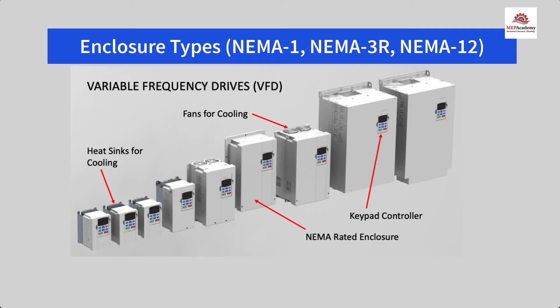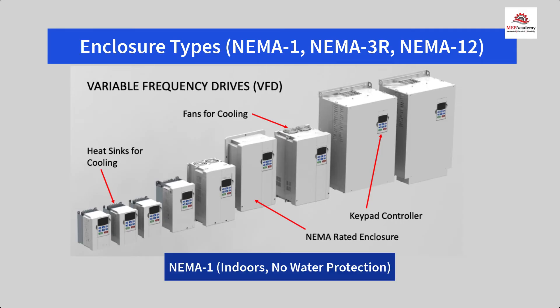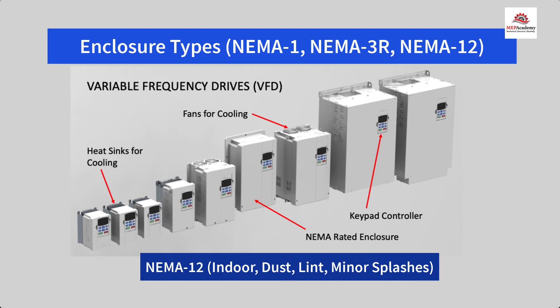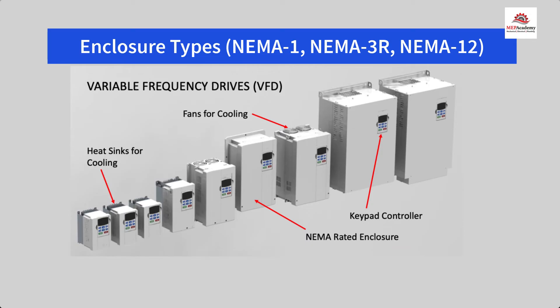NEMA 1 rated enclosures are made for indoors with no water protection. NEMA 3R is rated for indoor or outdoor use where rain, snow, or ice may form. NEMA 12 is rated for indoors with dust, lint, and other dirt circulating in the air along with minor water splashes. There is an enclosure for any environment — these are just three of the most common, and they get more expensive as the environment gets more hazardous and dirty.